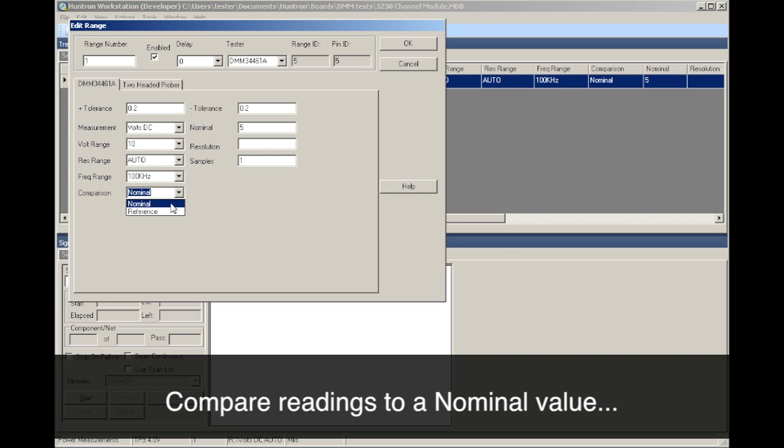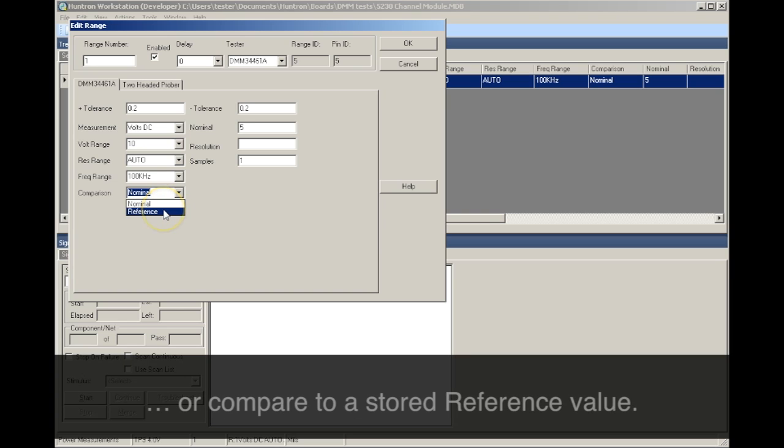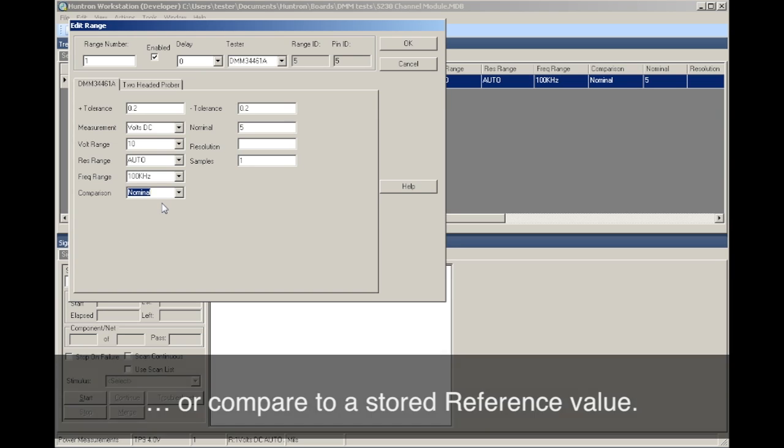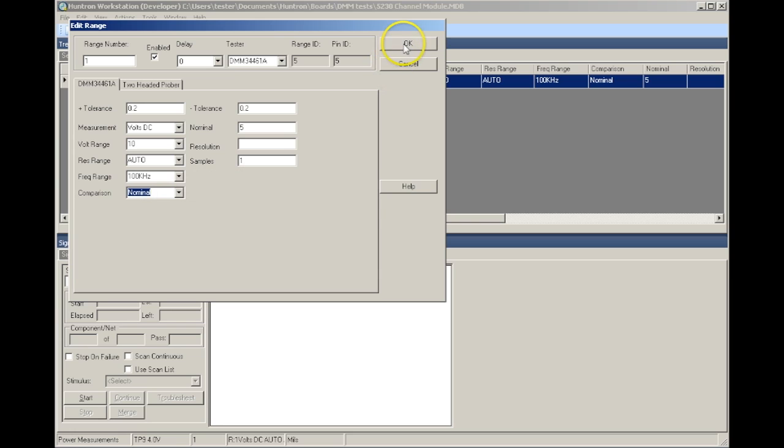As an alternative, you can use a reference measurement that is taken from a functional assembly and stored in the test database. When the test is run, measurements will be compared to the reference measurement and indicate a pass or fail. In this example, a nominal value will be used.